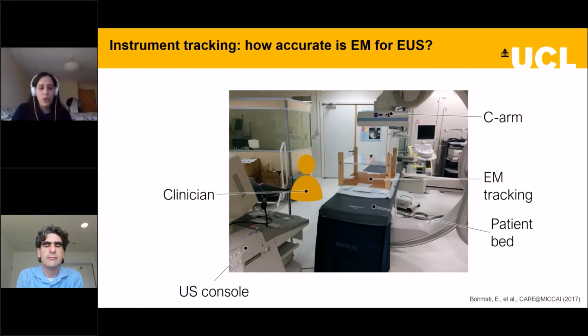And this is important because we know as a fact that nearby objects can affect the accuracy of tracking. In our case, the sensors will be inside the working channel, and the endoscope itself can affect the accuracy. But in addition to the endoscope, other elements that are in the endoscopy room, such as the C-arm, the patient bed, the ultrasound console, and the clinician itself might affect the accuracy of the tracking. Such that at the end, our electromagnetic field can be slightly distorted.